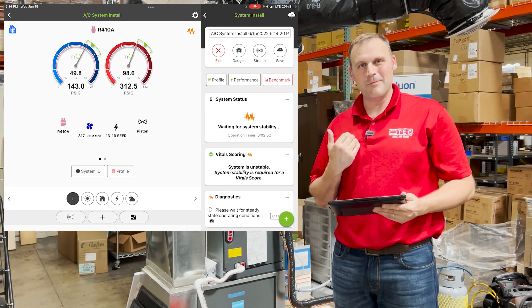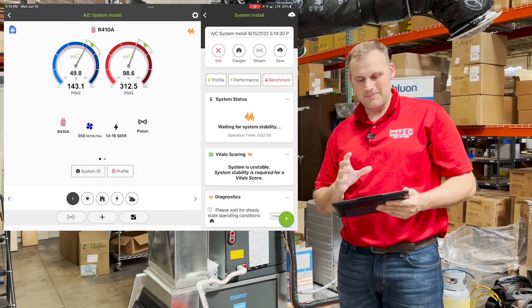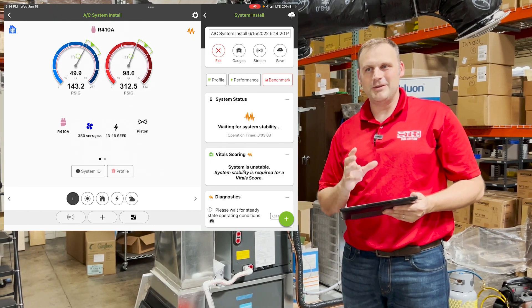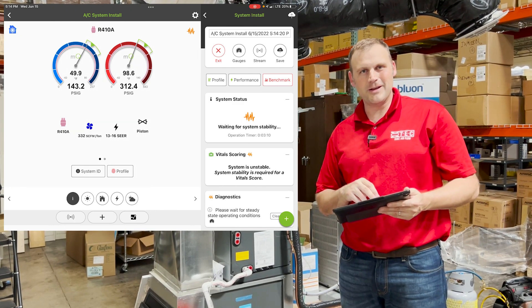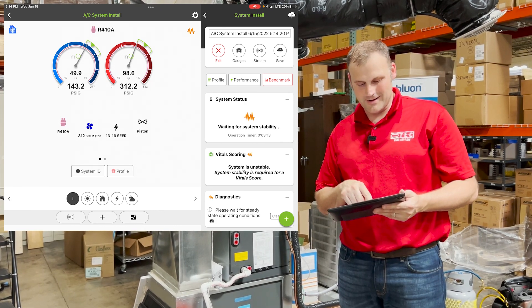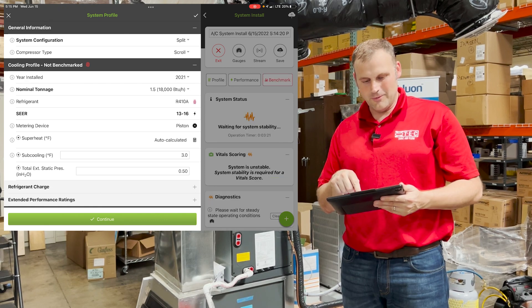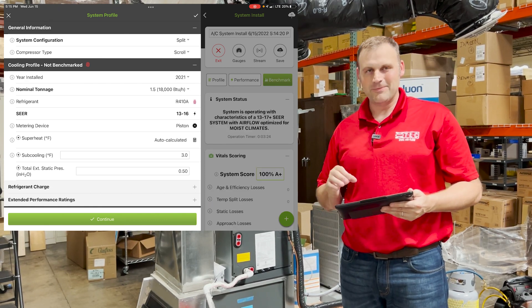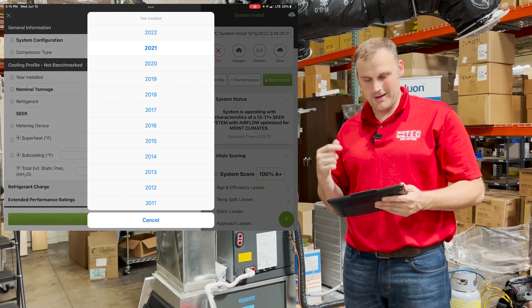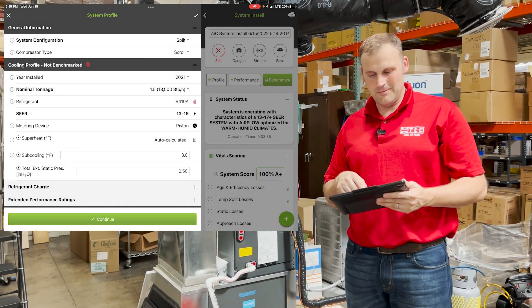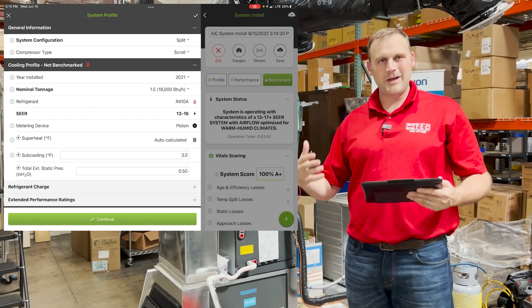Now here's the most important part, in my opinion — it's the profile. We've been here, we have this system, but let's say we haven't touched this system before. If you're a MeasureQuick classic user and you go right to the job and jump into the gauges, there's a profile button in the information screen. You click profile — that stuff needs to be entered. System configuration: it's a split system, scroll compressor, a 2021 unit, 1.5 ton BTU air conditioner, R410A refrigerant. This has all been entered because we've been here before, but if we haven't, we have to do this.